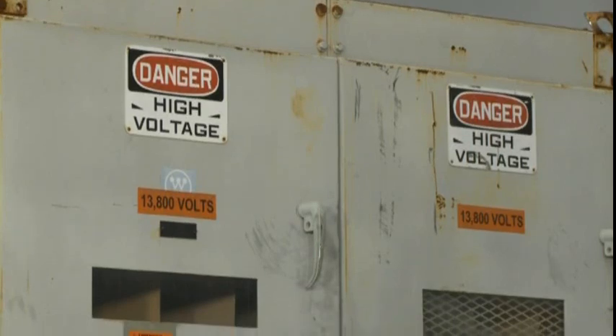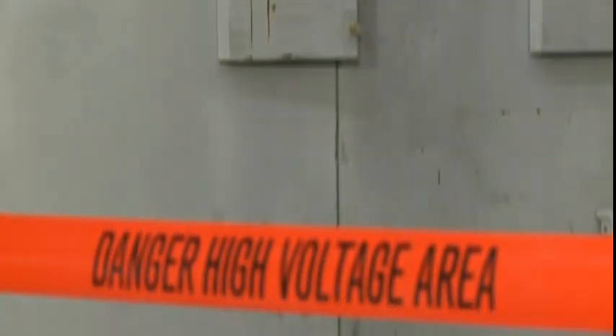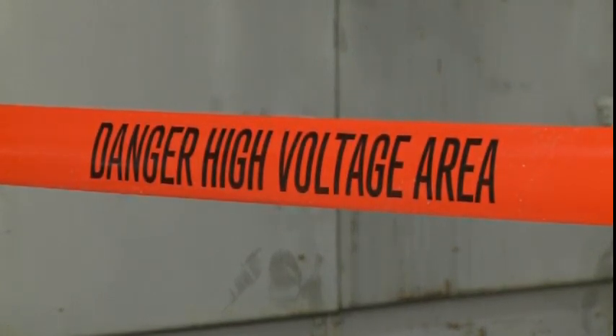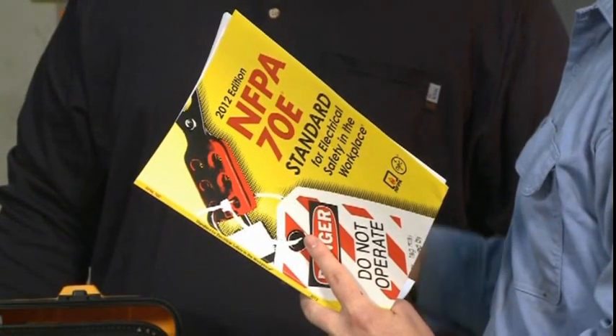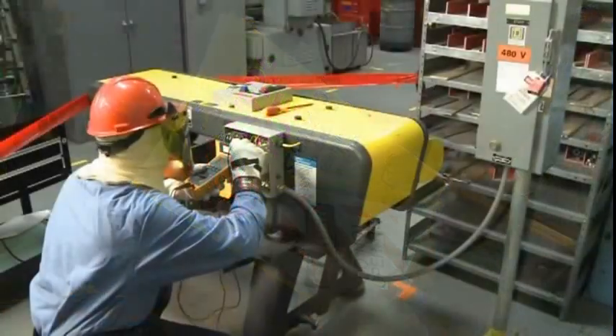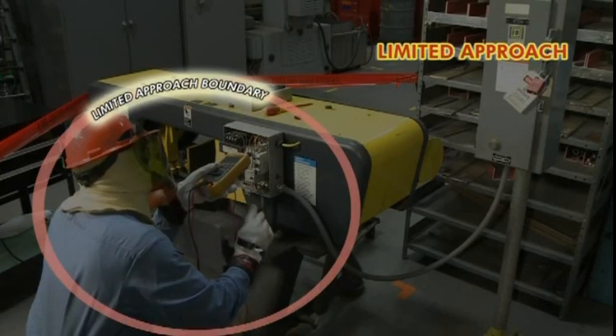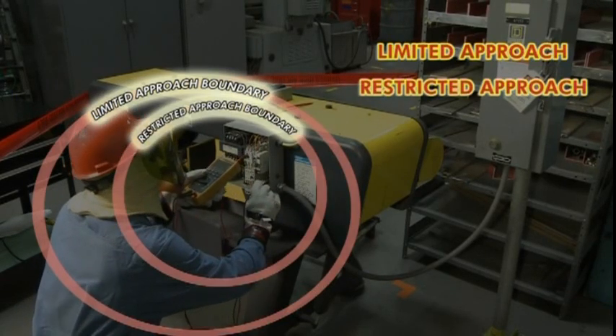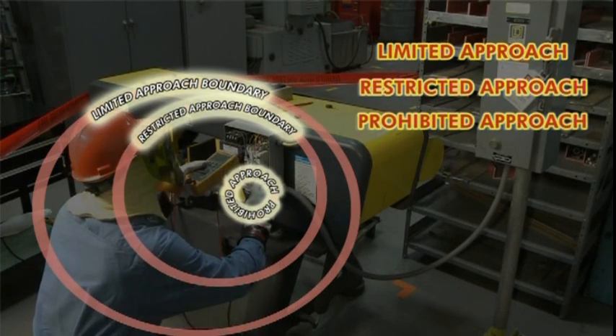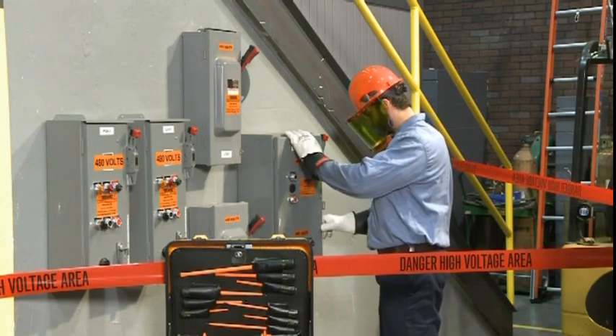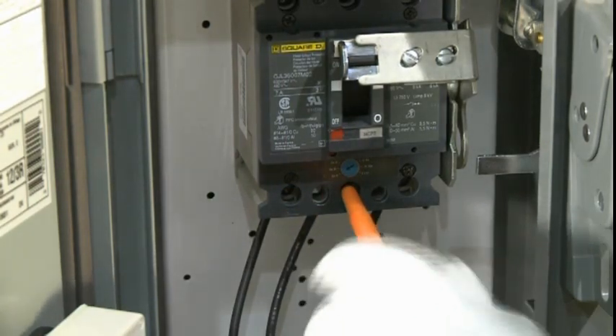Next, we will discuss safe work practices and approach boundaries for electric shock and burn hazards, beginning with shock protection. One tried and true method to avoid being shocked is to stay a safe distance from energized conductors or parts. In keeping with this safety principle, NFPA 70E establishes 3 approach boundaries: the limited approach boundary, the restricted approach boundary, and the prohibited approach boundary. The distance from an energized part to each of these boundaries increases as voltage increases. Before crossing these boundaries and moving closer and closer to exposed energized parts, workers need increasing levels of qualifications, protective equipment, and permits.